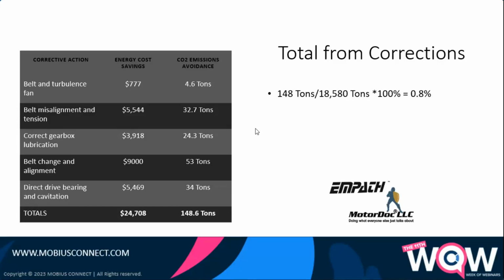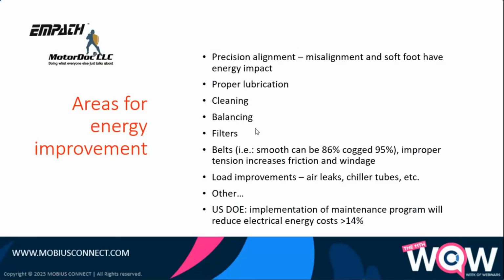Now, for the same plant, let's take a look at an overall application, reduction of harmonics in the system. Areas for energy improvement first: precision alignment. Misalignment, soft foot have a very definitive energy impact. Proper lubrication has a huge impact. Cleaning, balancing, and doing filters also has a huge impact. Belted applications, including going from really old, like big D belt applications to more modern, more energy efficient belt applications, all have an impact on the reliability of the machine and energy costs. All the load improvements, air leaks, chiller tubes, et cetera.